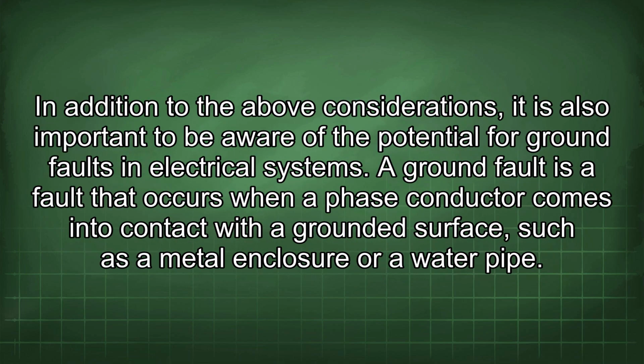In addition to the above considerations, it is also important to be aware of the potential for ground faults in electrical systems. A ground fault is a fault that occurs when a phase conductor comes into contact with a grounded surface such as a metal enclosure or a water pipe.